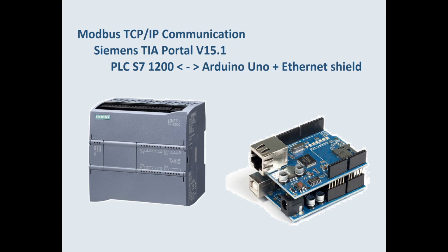It's a good idea to know a little bit about the Modbus protocol. I will explain the basics, but for more in-depth information, check the web. Modbus is a master-slave protocol. Master is also called client, and the slave is called server, which is a little bit confusing. Slave is listening on a given port, master is responsible for initiation of the connection.